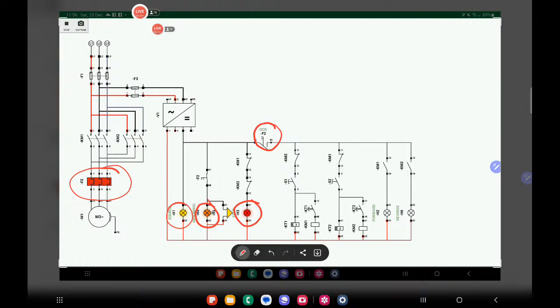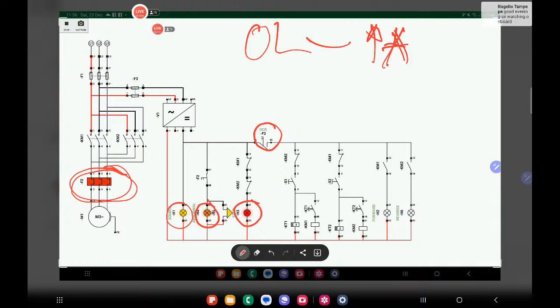So in this condition, if I want to test the circuit in a live condition, of course, there are limitations. If there's an alarm of overloading, or the circuit is overloading, if this F2 is activated, right? So there will be a high current, amperage onto your system. But you want to try which contact is having a problem, right? So the best way is to try to reset the system, but you have to investigate after, by not starting the control panel.